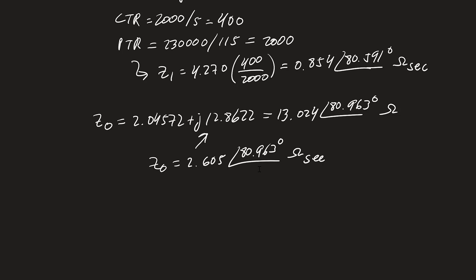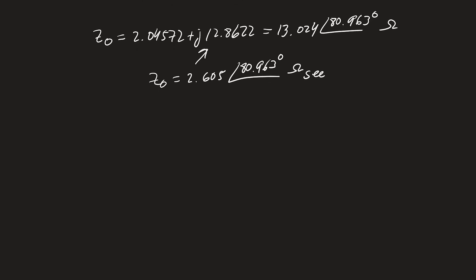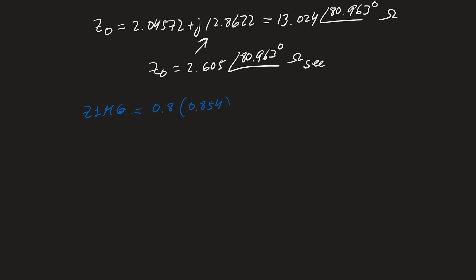Now let's calculate the reaches of the mho ground distance element. We use the positive sequence impedance — which is counterintuitive for a ground element, but we compensate using the zero sequence compensation factor. For zone one, Z1MG = 0.8 × 0.854 = 0.68 ohms secondary, rounding to two decimal places as the relay requires.